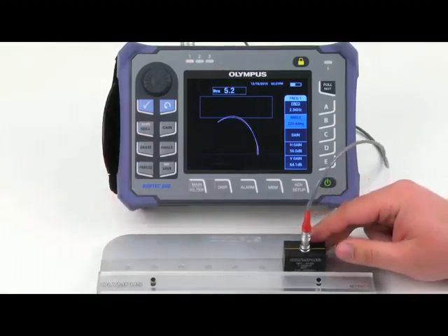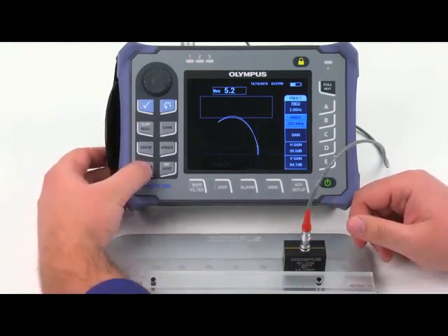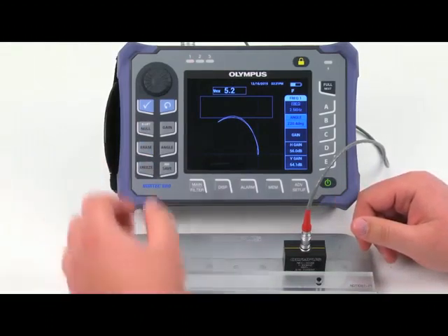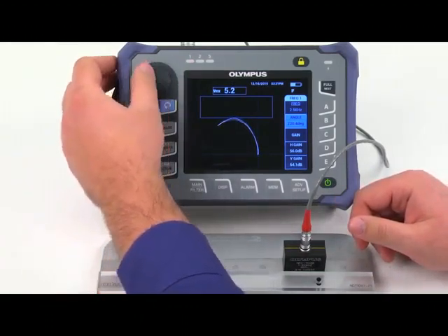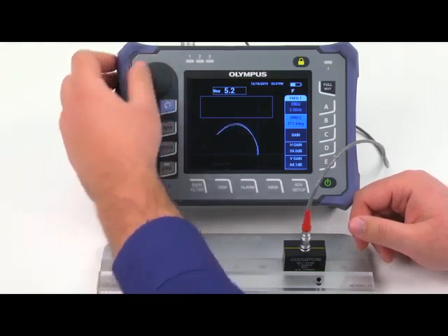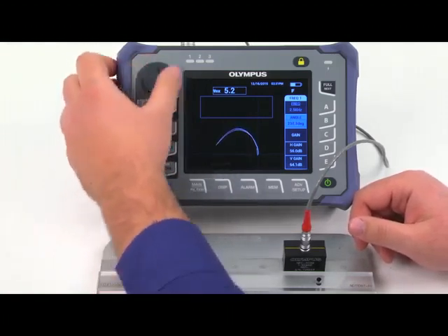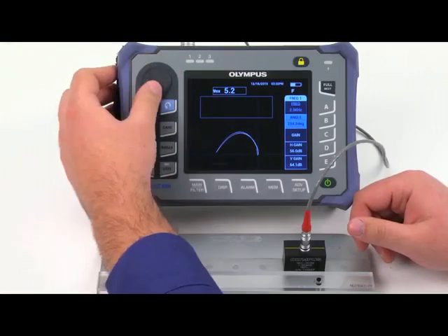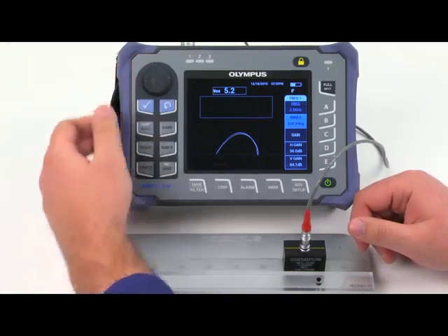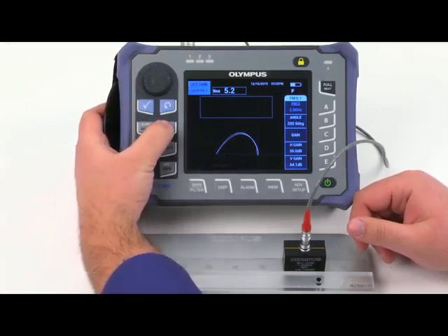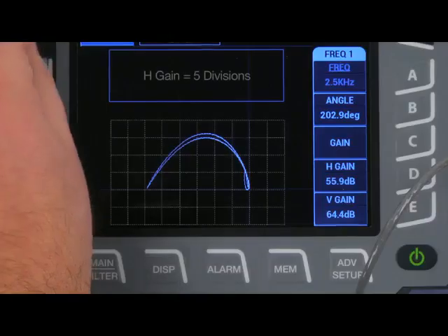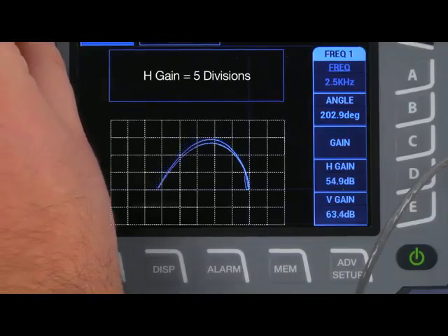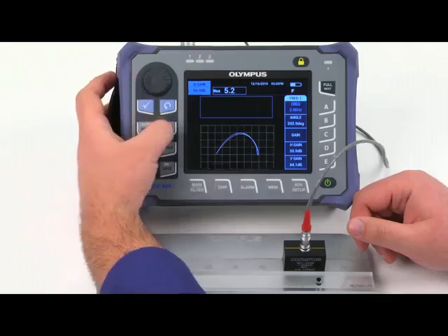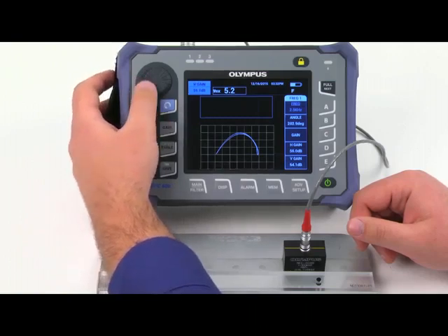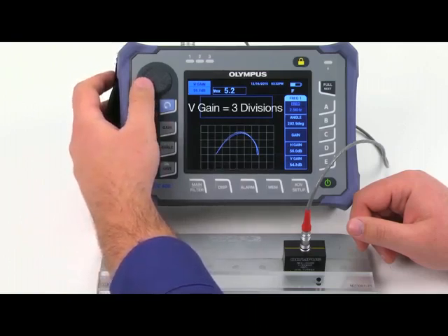Slide the probe to scan an undamaged rivet. Press freeze. Using the angle key and knob, adjust the signal so that the starting and end points are both parallel. Press gain twice and use the knob to adjust the horizontal gain. The H gain signal should cover 5 divisions. Press gain again and use the knob to adjust the vertical gain. The V gain signal should cover 3 divisions.